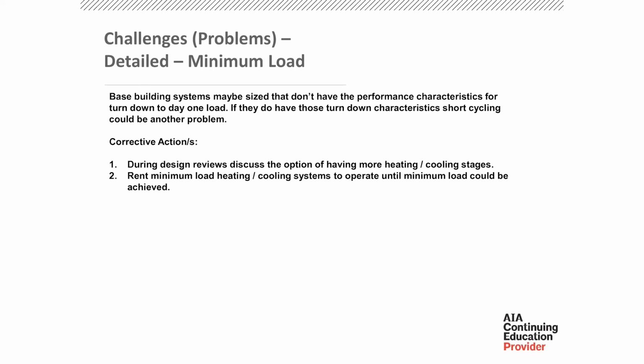Base building systems may be sized such that they don't have the performance characteristics for turn down ratios for day one. If so, even if they turn down, you'll have a problem with short cycling. So corrective actions are design reviews, discussing this operation, and having more heating and cooling stages, so you can have fewer nuisances. Rent minimum load or heating and cooling systems to operate until a minimum load can be achieved. So if you have a smaller fit out, you can pull temporary chillers or heaters or boilers into the system.